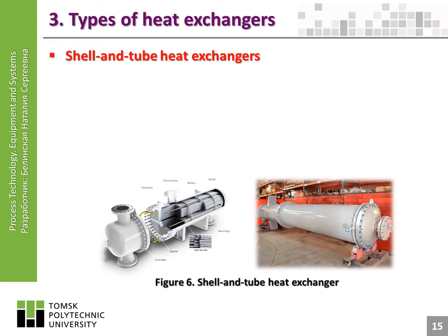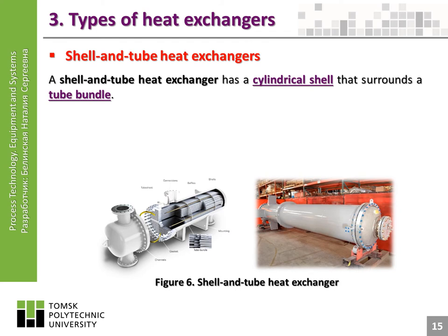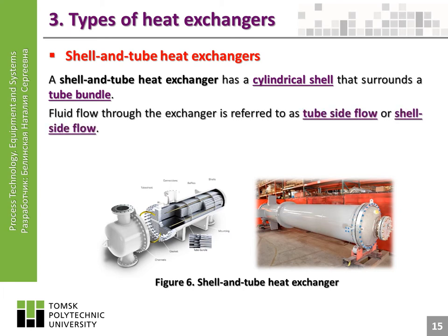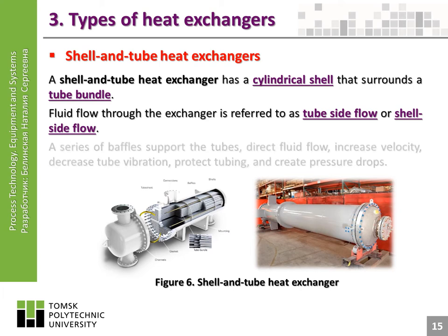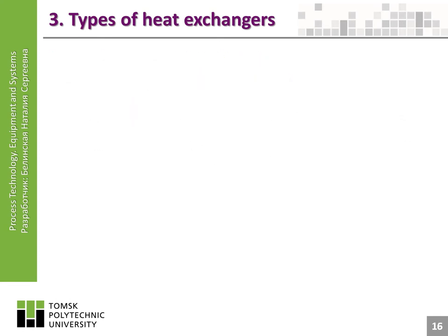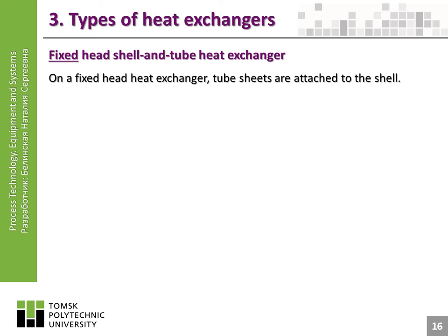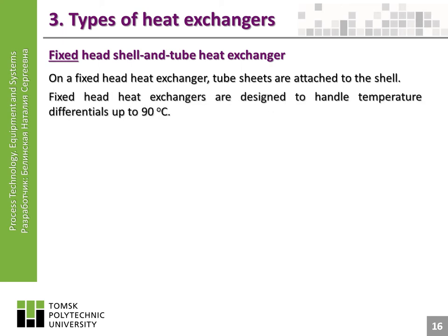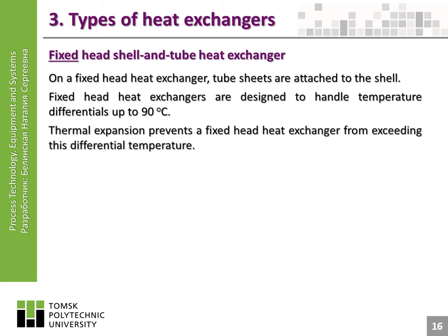Shell and tube heat exchangers. A shell and tube heat exchanger has a cylindrical shell that surrounds a tube bundle. Fluid flow through the exchanger is referred to as tube side flow or shell side flow. A series of baffles support the tubes, direct fluid flow, increase velocity, decrease tube vibration, protect tubing, and create pressure drops. On a fixed head heat exchanger, tube sheets are attached to the shell. Fixed head heat exchangers are designed to handle temperature differentials up to 90 degrees Celsius. Thermal expansion prevents a fixed head heat exchanger from exceeding this differential temperature. It is best suited for condenser or heater operations.